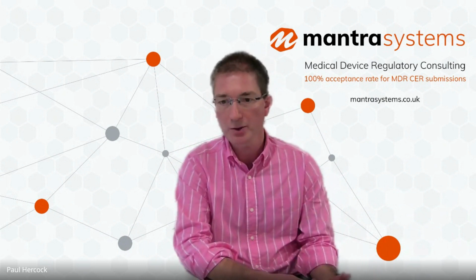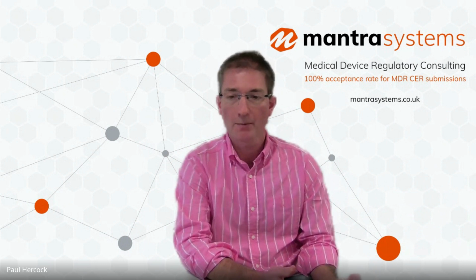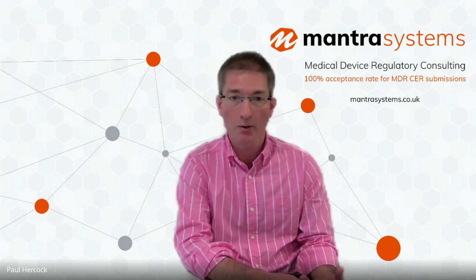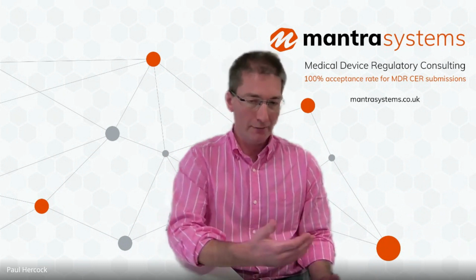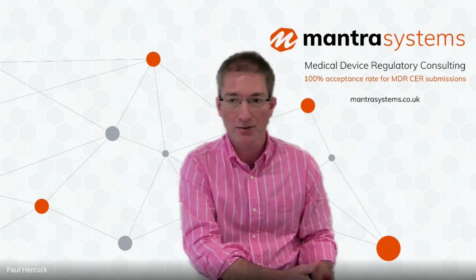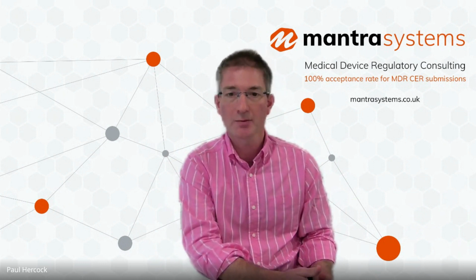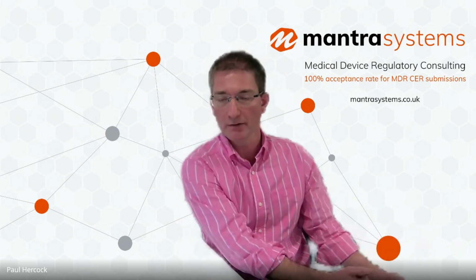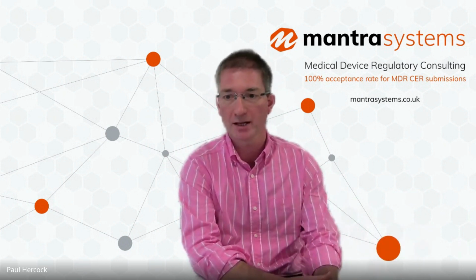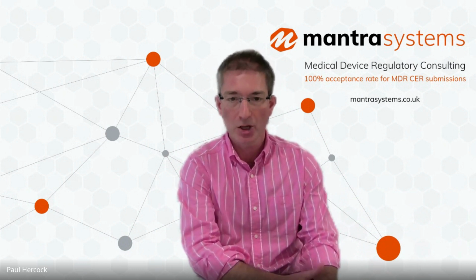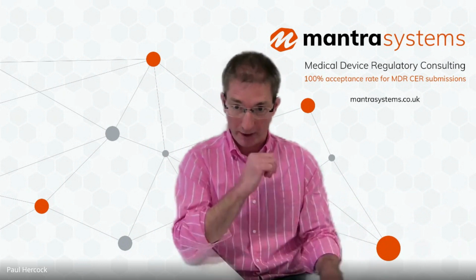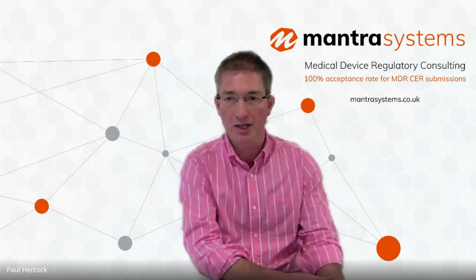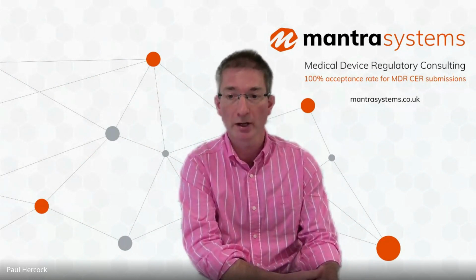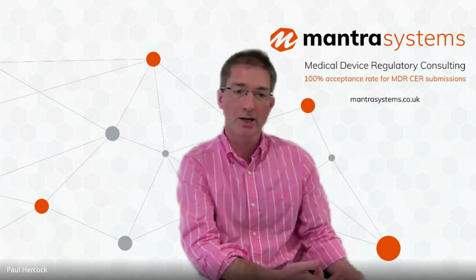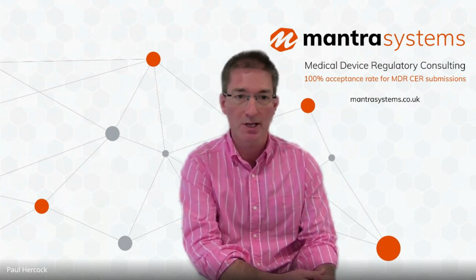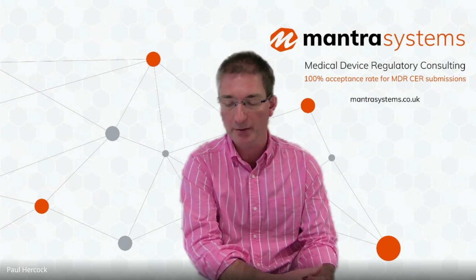So to claim equivalence successfully under MDR, the first step is to make sure that you meet the baseline requirements. By that, I mean that if you look at the regulation, if you have a class 3 device, you need a contract in place with the manufacturer of the equivalent device, showing that you have full unfettered access to the technical files. That's not a problem if you're claiming equivalence to your own device, but I fail to foresee a universe in which a competitor would give you access to the technical files. So in that situation, to all intents and purposes, it is now impossible to claim equivalence for that reason.